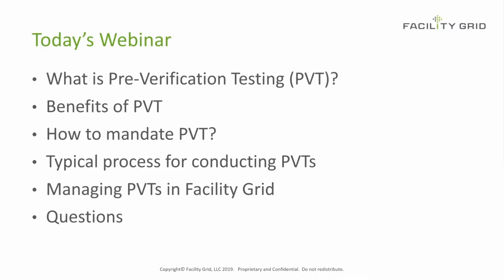This could result in failed FPTs, as commissioning agents are still responsible to verify that the equipment operates per the design documents and the approved control submittal, unless the engineer of record actually approved the required modifications in the sequence of operations. So during completion of PVTs, if contractors determine that there are any deviations in programming from the design documents, approved submittals, or testing procedures, they can notify the team and resolve those deviations ahead of the FPTs. If this happens, this would save time for everyone and would minimize any potential delays during the FPT process.